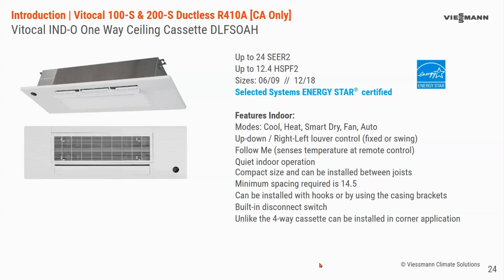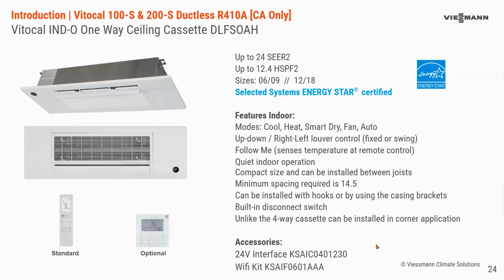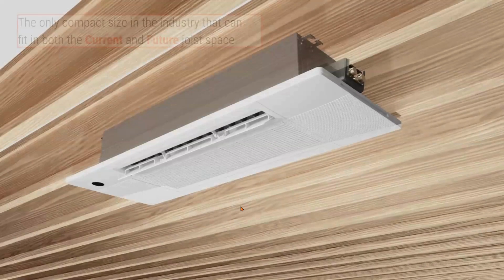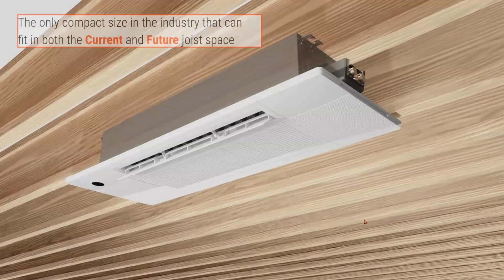And unlike the 4-way cassette, this can be installed up against a corner in a hallway because it does not require the same clearances as a 4-way cassette. This unit is compatible with the 24-volt accessory as well as the Wi-Fi kit. There is a standard wireless controller, optional wired controller. There's your image there, showing how that installs in between joist spaces.